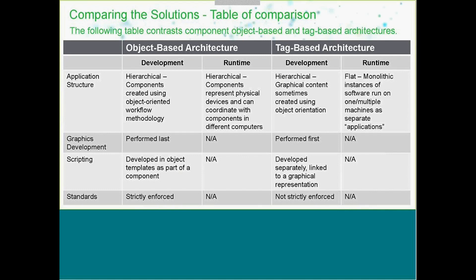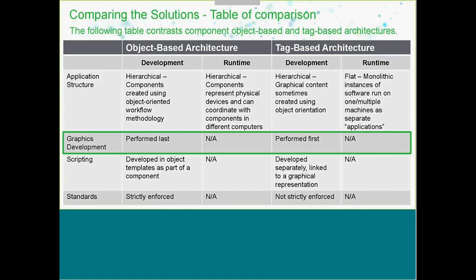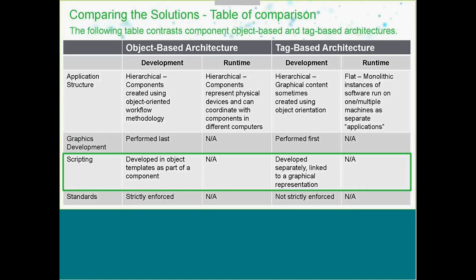Comparing application types in terms of development: in an object-based solution, graphics are created last. We create our template structures, create the instances of those structures, and then create the graphics to display that data at runtime. With a tag-based solution, we create that graphic first, then add the functionality required around the graphic, connecting tags and connecting those tags to our I/O in the PLC. Scripting is developed inside object templates in an object-based approach, whereas in a tag-based architecture it is developed separately in a scripting environment.